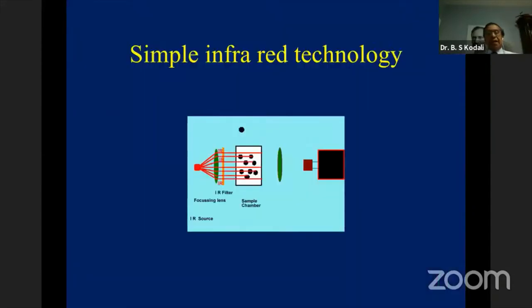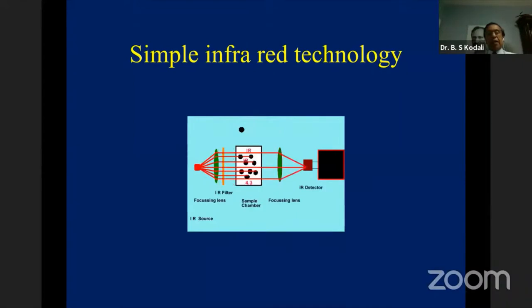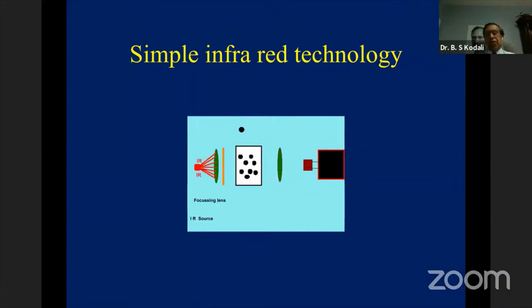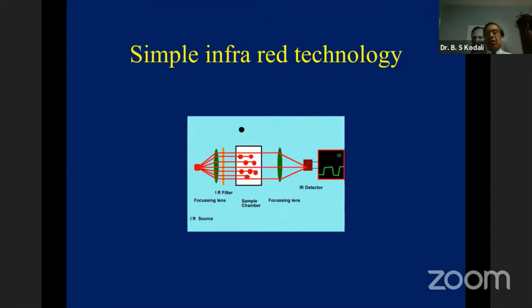A little bit of physics: CO2 is a polyatomic gas and therefore it absorbs infrared light. There is a source of infrared in the unit. The CO2 absorbs the infrared light, the balance of infrared light is measured, and the difference between what is given and what is measured is quantitated into a CO2 waveform, which you see on your monitor on a regular basis.